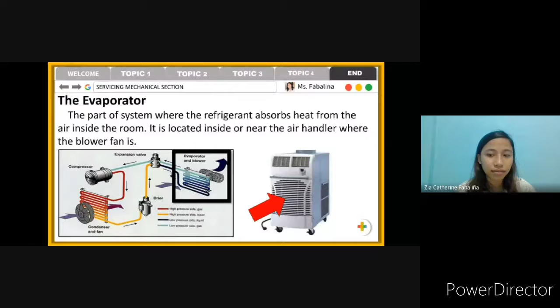So first trouble of our evaporator is fan burns out. So it leads to evaporator fan to burn out when fan motors are overworked and lack of maintenance. So they tend to go bad and burned out. Next is dirty evaporator coil. So from the dust inside of our room. So yung ating condenser is encountered dust issue also, and so our evaporator too. For example, yung mga mahihilig sa aso at pusa, yung kanilang balahibo is maaaring maging sanhi ng ating evaporator to become dirty or reason to form any soiling, which will cause para hindi gumana ng maayos ang ating evaporator.